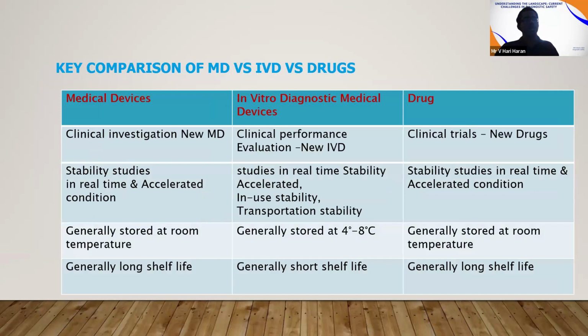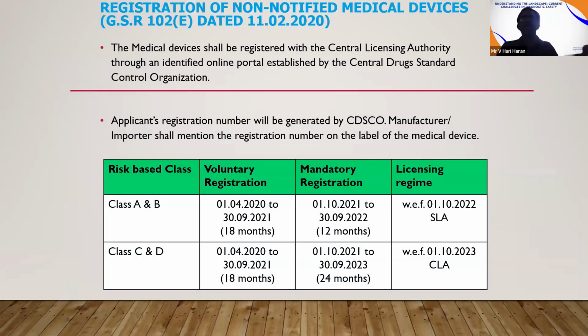For medical devices, we have to analyze stability studies in real-time and accelerated conditions. For IVDs, we have to have real-time stability, in-use stability, transport stability and so on. We need to assess the causes of failures and how to improve. For drugs, we discuss stability studies in real-time and accelerated conditions. Medical devices are generally stored at room temperature, apart from some misconceptions. But IVDs should be stored at 4 to 8 degrees Celsius, and drugs at room temperature or, for specific drugs, according to the manufacturer's instructions. Medical devices can have a longer shelf life, IVDs a short shelf life, and drugs a longer shelf life. Each is unique and cannot be regulated in the same way.